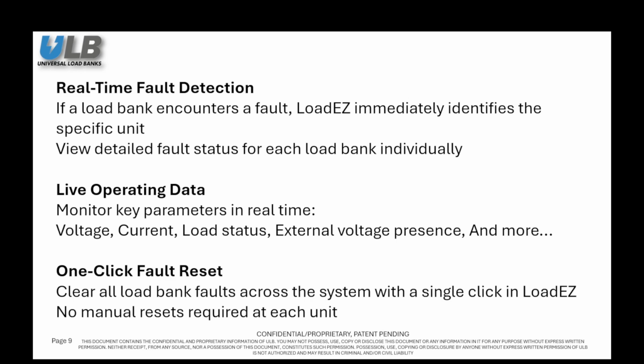LoadEZ provides real-time fault detection and live monitoring to keep your system running smoothly. If a load bank encounters a fault, LoadEZ immediately identifies the specific unit, allowing you to view detailed fault status for each load bank. Individually, you can also monitor key parameters in real time, including voltage, current, load status, external voltage presence, and more. This gives you full visibility and control, right when you need it most. With the LoadEZ clearing system, clearing faults is simple and fast. You can reset all load bank faults across the system with a single click. No need to manually reset each unit.